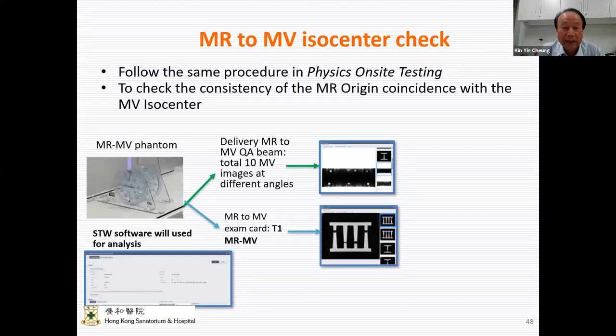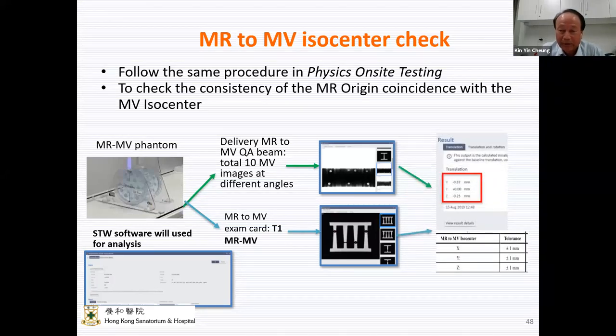And then we run an MR image on the phantom, and the software will compare the two isocenters and indicate whether it's a pass or fail. And the tolerance is 1 millimeter. In this case, we get 0.3 millimeter in x-axis and zero error in y, and 0.27 millimeter in z-axis. So it's a monthly test on the geometrical accuracy of the isocenters.